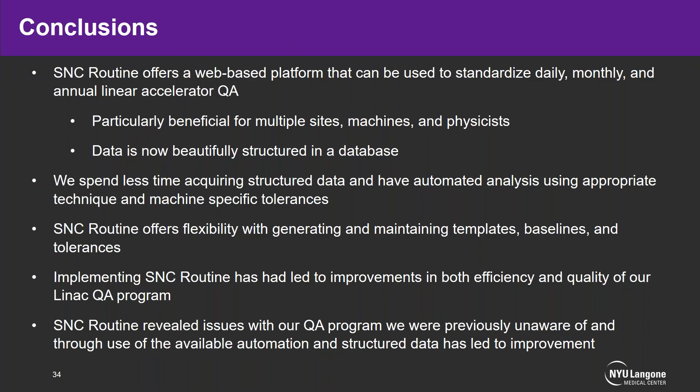In conclusion, SNC Routine offers a web-based platform to standardize daily, monthly, and annual linear accelerator QA. It's proven particularly beneficial for multiple sites, machines, and physicists, and all our data is now beautifully structured in a database rather than scattered across different locations. We spend less time acquiring data and now have automated analysis using appropriate technique- and machine-specific tolerances. Implementing SNC Routine has led to improvements in both efficiency and quality — normally making something more efficient suffers a quality loss, but we found it boosted both. SNC Routine also revealed issues with certain aspects of our QA program we were previously unaware of, which we were able to improve through automation and structured data.